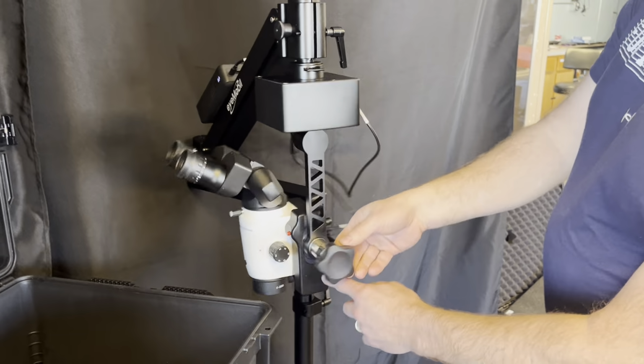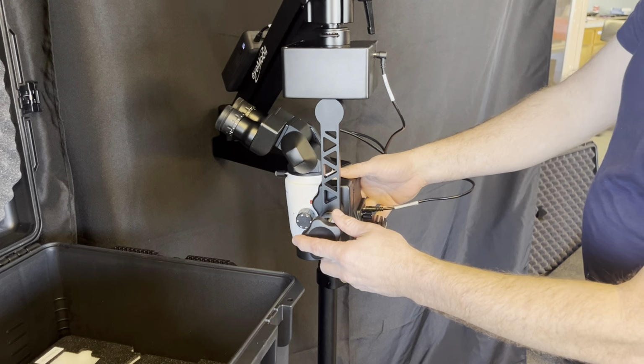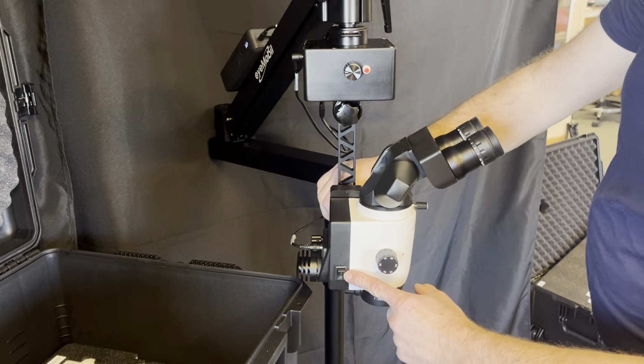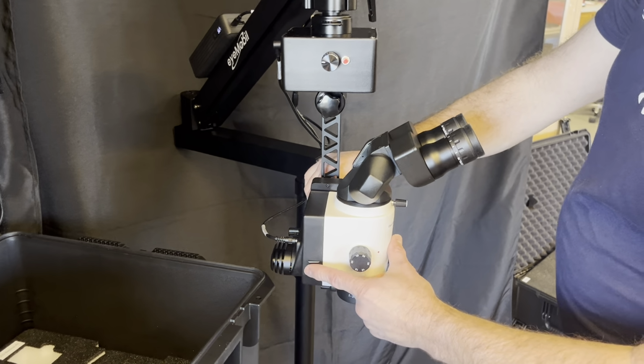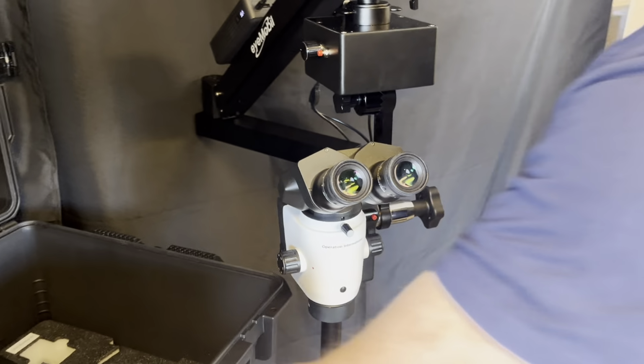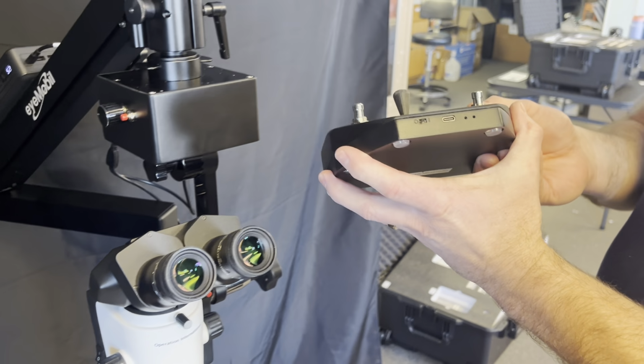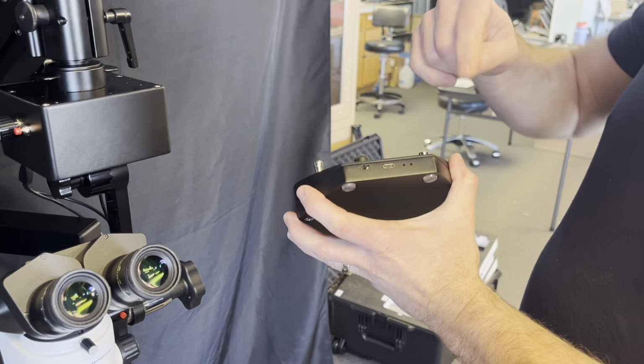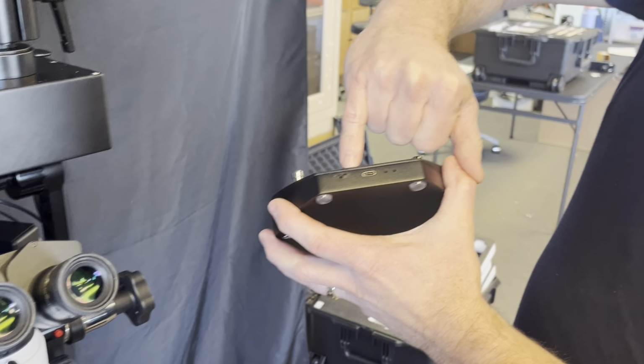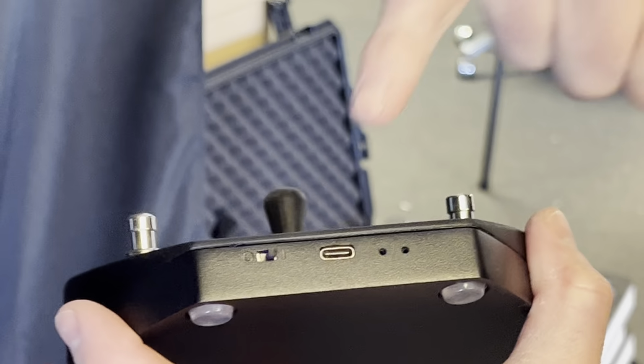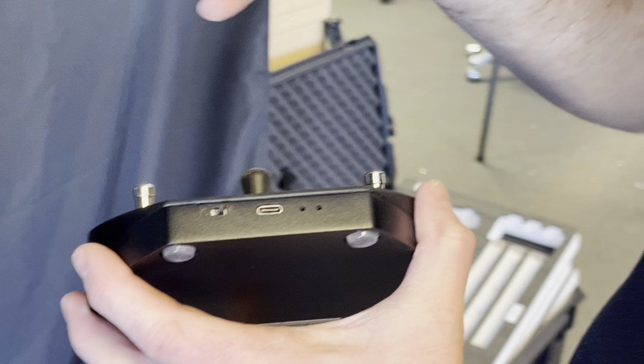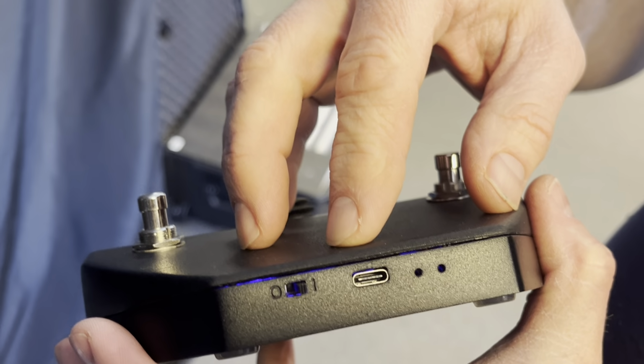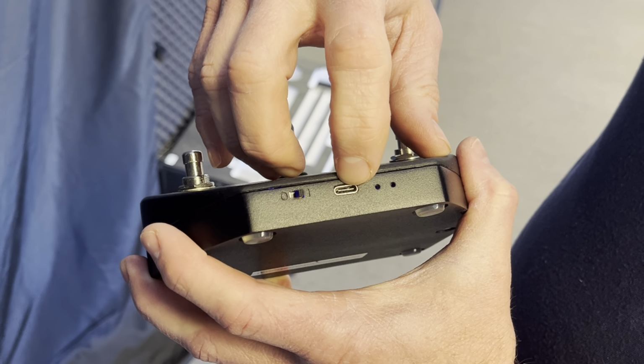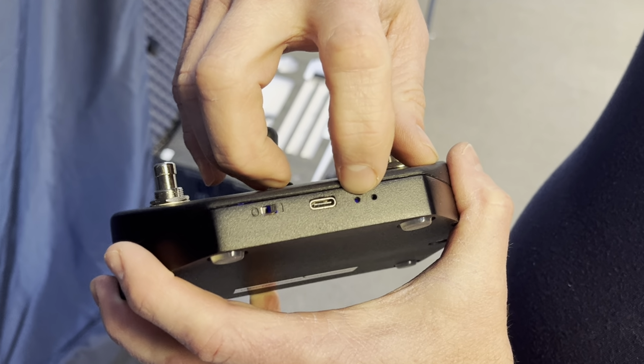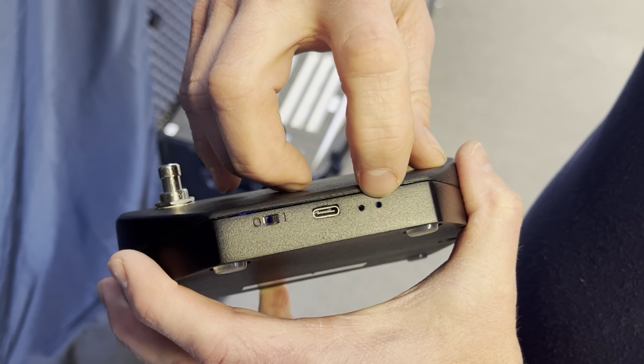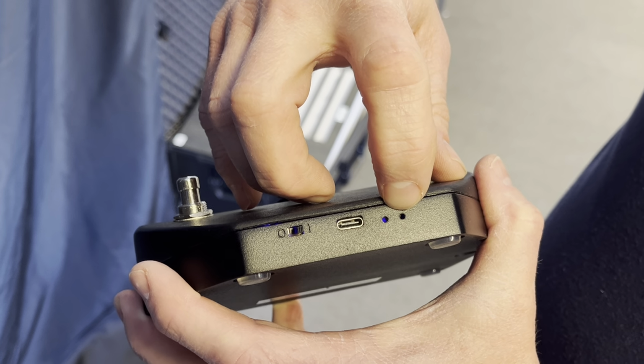The Z unit, the wireless Z unit, which is on this side of the scope, will not work unless you have the power switch on, which also powers the surgical light. So we turn that on, and we also take out the foot pedal, which is stored in layer 4 of the microscope. There are 3 LEDs inside of this foot pedal. The first one is a blue one, which you can see glowing now, and that means that the foot pedal is powered. When we are charging the foot pedal with the USB-C connection, there will be a red LED indicating it's receiving charge, and then when it's fully charged, a green LED will light.